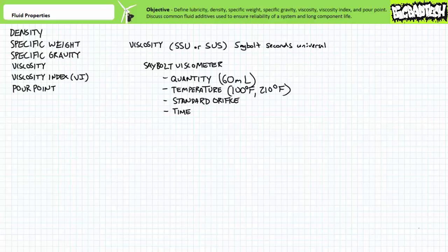This is the key to industrial viscosity measurements using a Saybolt viscometer. A quantity of the liquid under test, 60 milliliters, is allowed to drain through a standard sized orifice while at a constant temperature. Viscosity measurements are ordinarily performed using two different temperatures: 100 degrees Fahrenheit or 210 degrees Fahrenheit. For viscosity measurement of hydraulic oil using the 100 degree Fahrenheit standard, 60 milliliters of the oil under test is poured into a container and heated to 100 degrees Fahrenheit. The standard sized orifice is opened up, and the time it takes to empty the container is the viscosity measurement in units of SSU. A typical hydraulic oil might have a viscosity measurement of around 150 SSU.